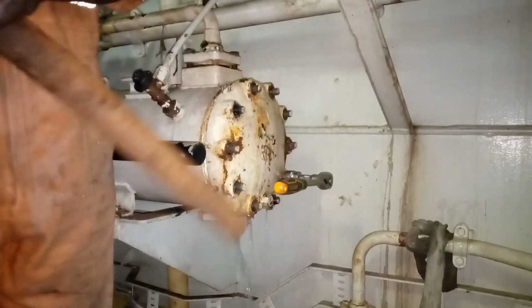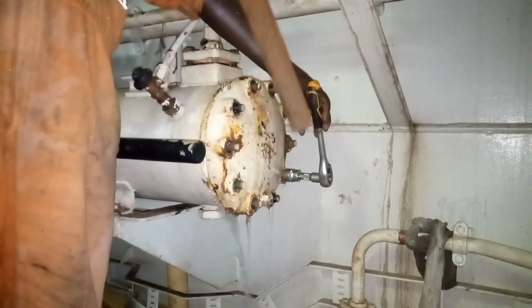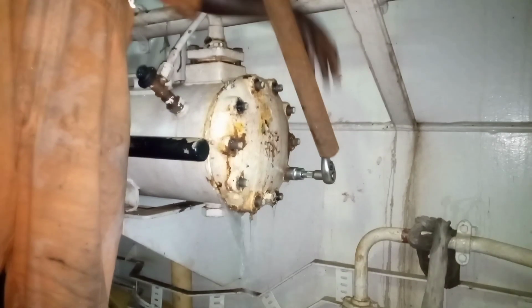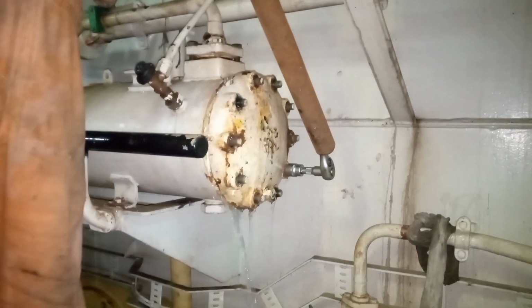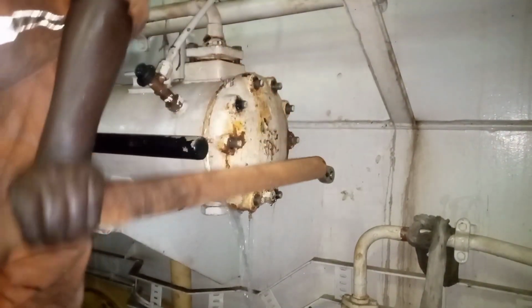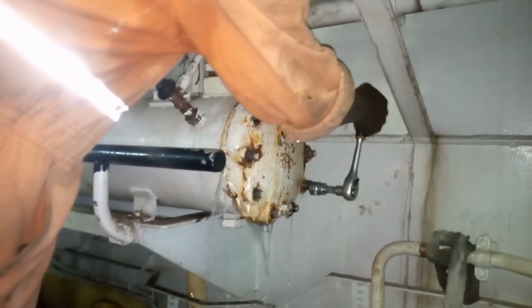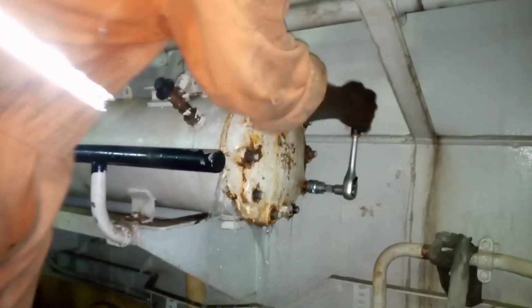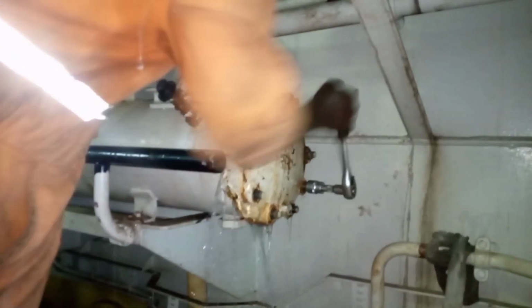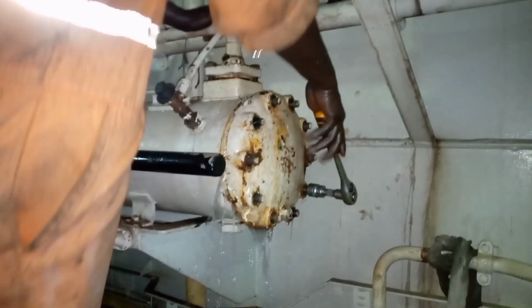Let's get started. This heat exchanger is used for cooling the air conditioning refrigerant, and so before we started servicing the heat exchanger, we had to close the seawater inlet valve, and also we switched off the refrigerant compressor.